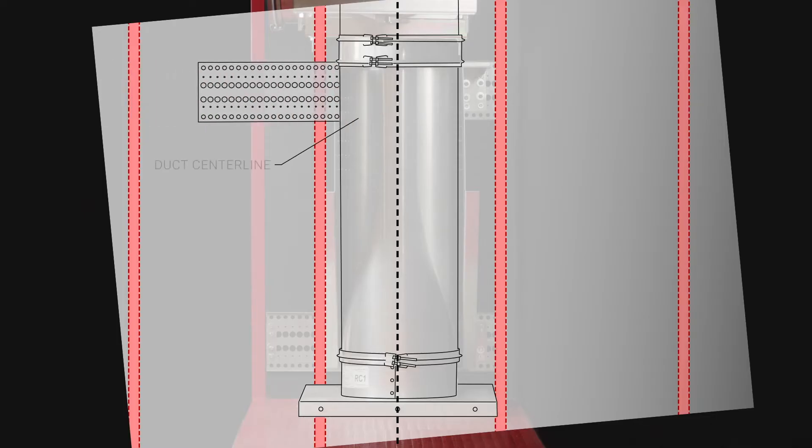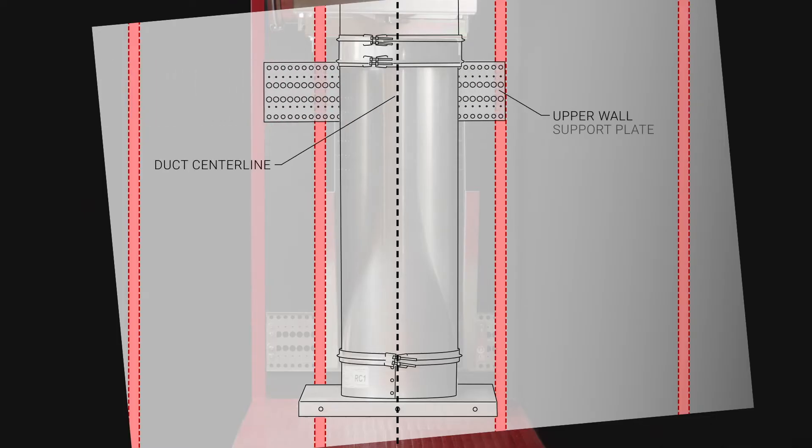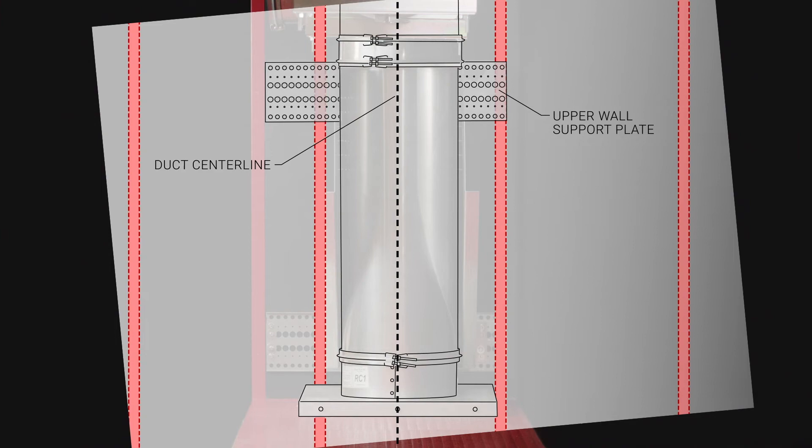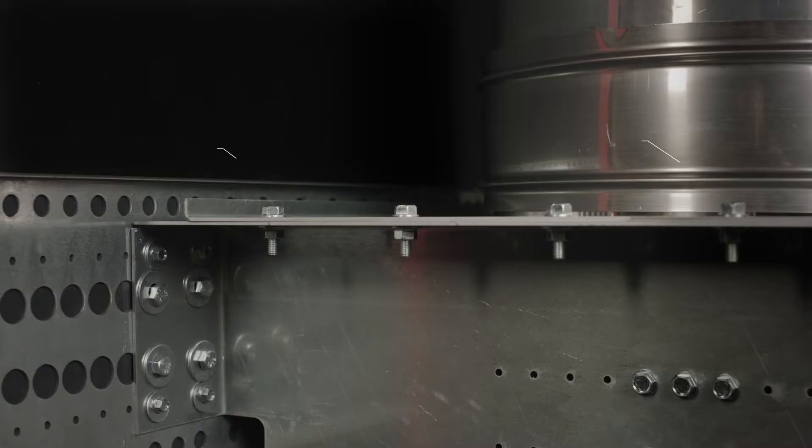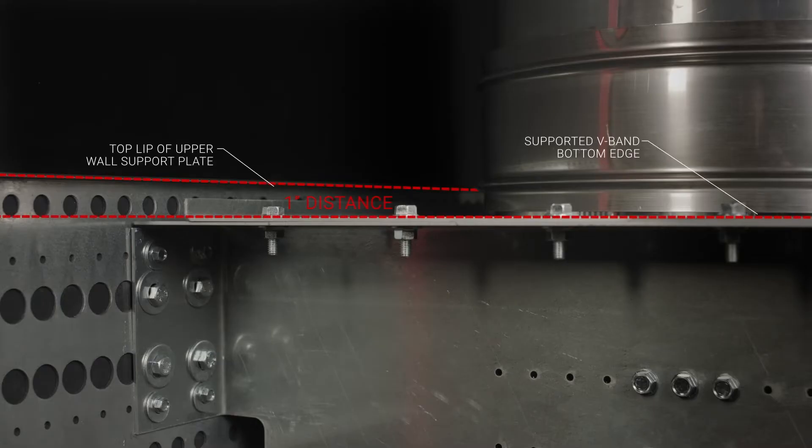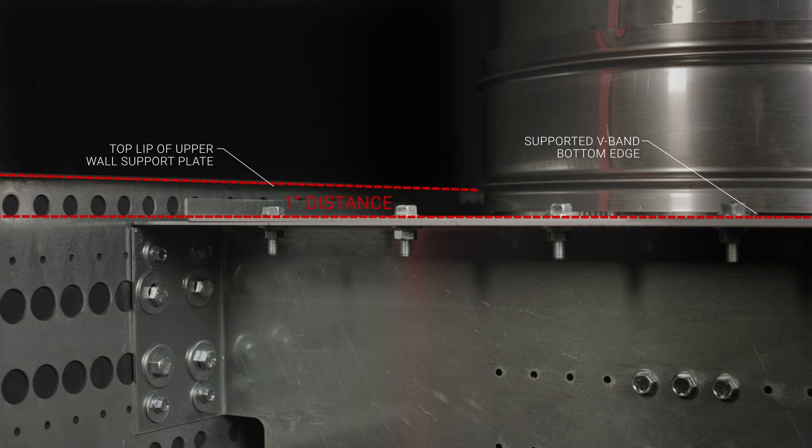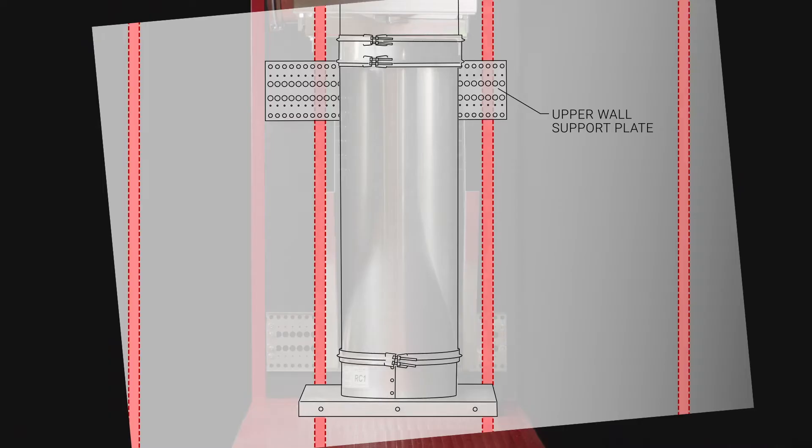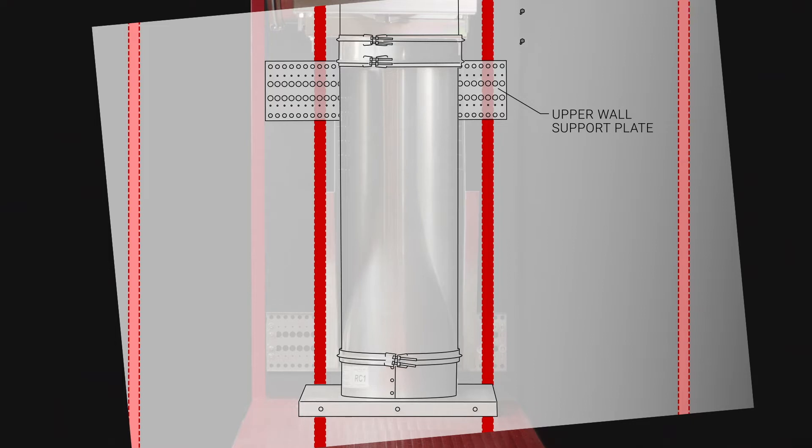Install the upper wall support plate centered behind the duct run with the top lip of the plate one inch above the bottom of the duct V-band you choose to support. When mounting into wooden or metal studs, the upper support must be mounted onto a minimum of two studs.